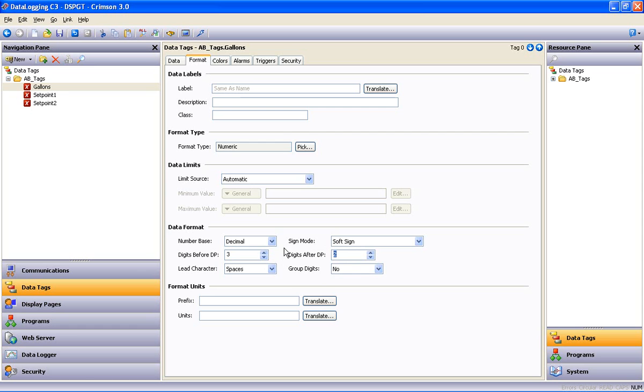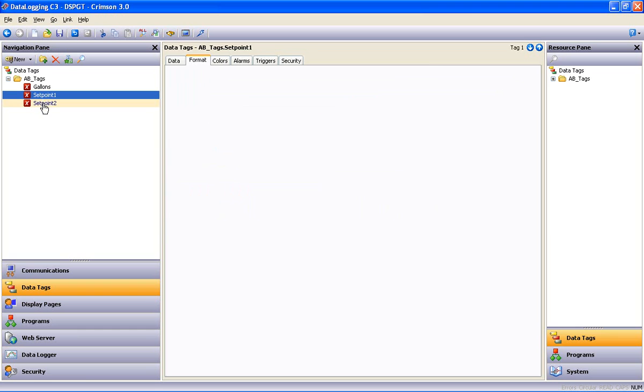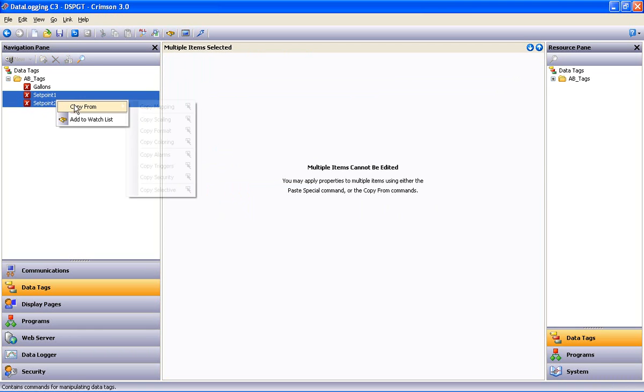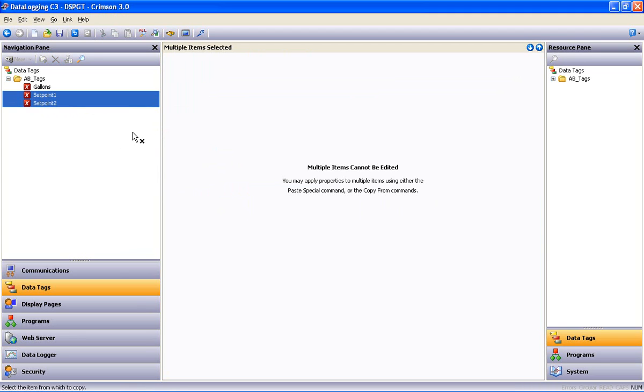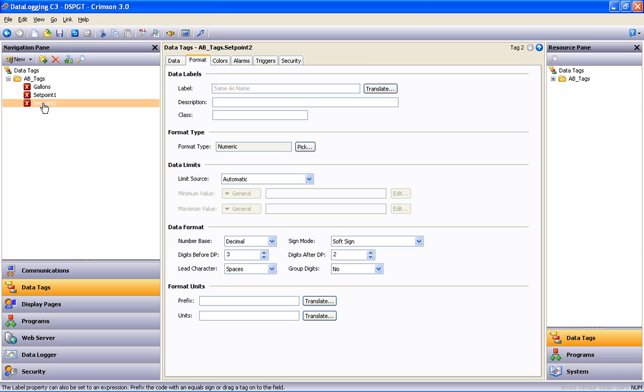Now, what if I want to change the formatting on the rest of my tags to match those changes? Not a big deal on two tags to do them one at a time, but what if I had 30 to change? Holding down my Shift key, I multiple select the other tags, right-click on them, and select Copy From. Now it's waiting for me to point at a source for the formatting. So I point at Gallons and click, and I'm told that the selected properties were applied successfully. And now if I look at each tag, you can see the formatting type and the data formatting has changed accordingly. A big time saver if you need to make changes to a long list of tags.